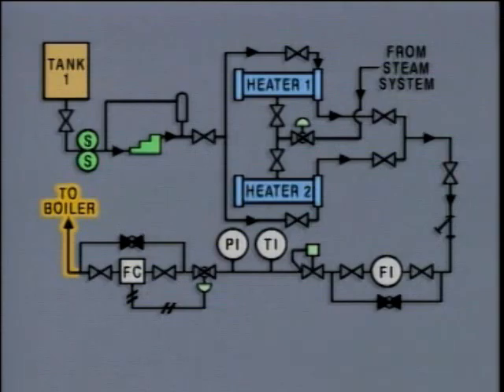System diagrams can be a big help when you're finding your way around a process system for the first time. As an example, let's follow along on a diagram as we trace the fuel oil system for an oil-fired boiler. The fuel oil is stored in tank number one. We'll begin here and follow the flow path of the oil from the tank to the boiler. Oil leaves the tank through an isolation valve. The first component the oil comes to is shown as two circles each containing the letter S — the symbol for a duplex strainer, which removes solid particles from the fuel oil. From the strainer, the fuel oil flows to a positive displacement pump. There's a pressure relief valve at the pump discharge that routes oil back to the suction side of the pump if the discharge pressure gets too high.